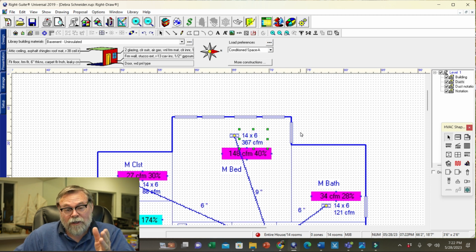That's what the computer says, because this room has 4 windows in the back that face west, so this room has a lot of load. She's only getting 40% of the air she needs. The computer told me, when I put a duct over to it, that it needs to be a 9-inch. I'm sure it's probably not a 9, it's probably a 7, maybe an 8, but I doubt it's even an 8. It's probably a 7-inch duct. So we did a room to room that's told us what we need.